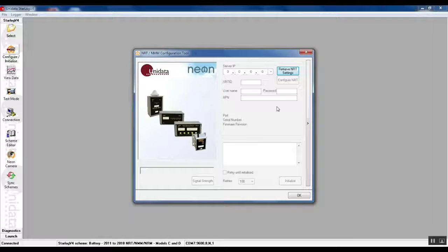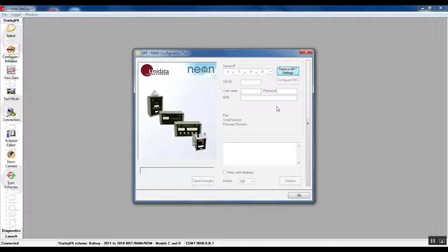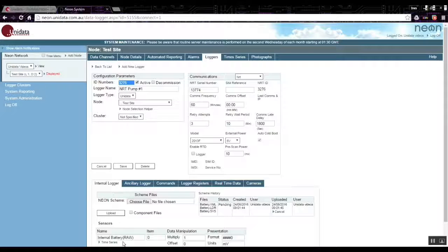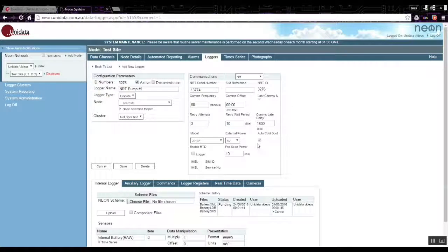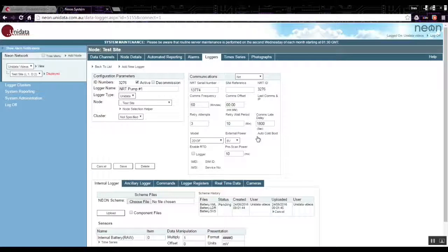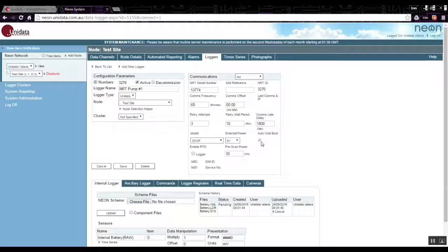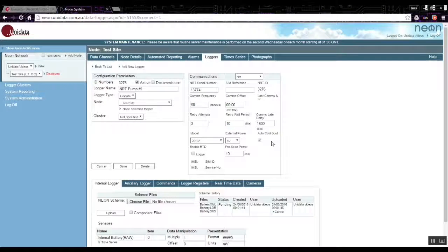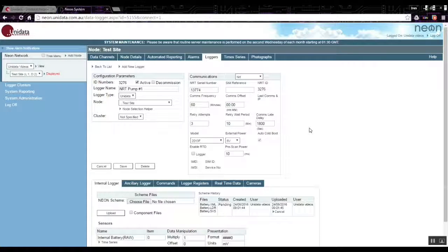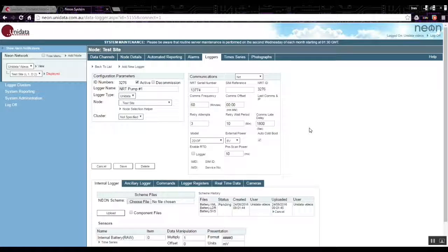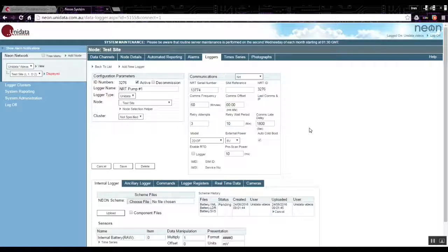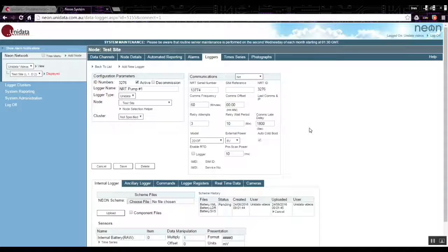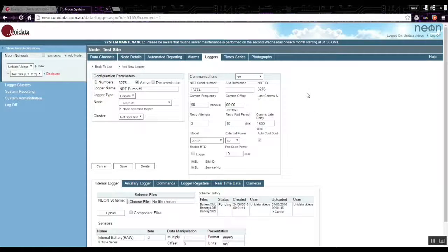You always have to make sure that the red light on the NRT is not flashing. If it is flashing you have to wait for it to stop flashing. Most NRTs are configured on the server. If I show you that again briefly on the loggers tab, there's a tick box on the right here that says auto cold boot. Most users have that pre-configured and what that tick box does, it means that when you turn an NRT on it will automatically try to connect to the neon service as soon as it powers up.